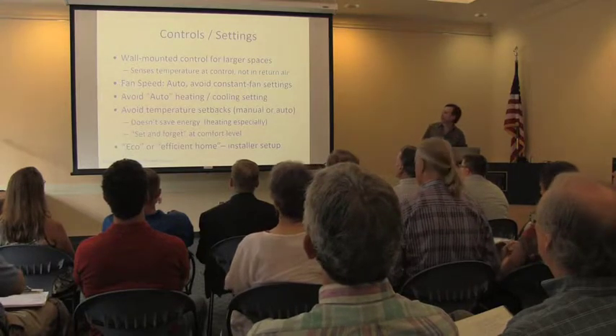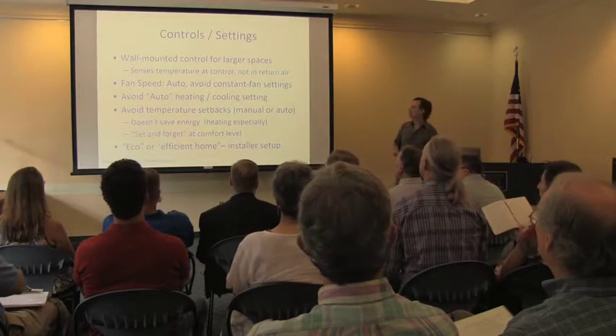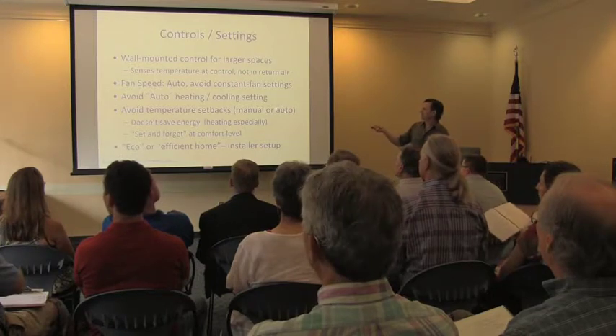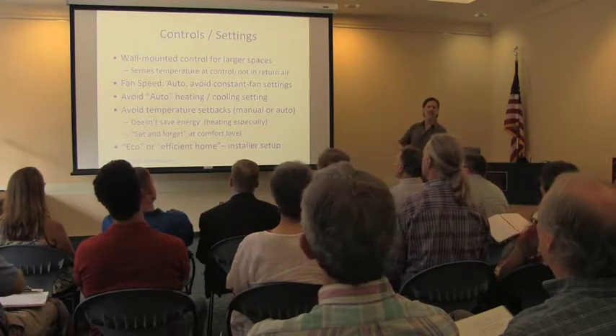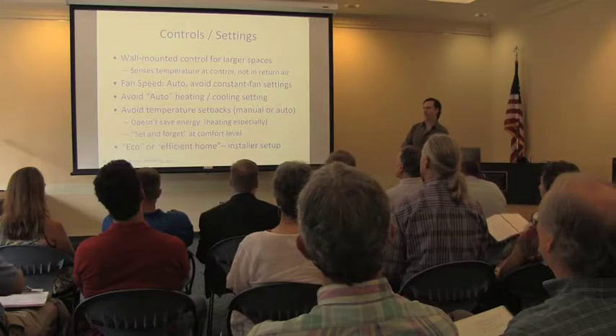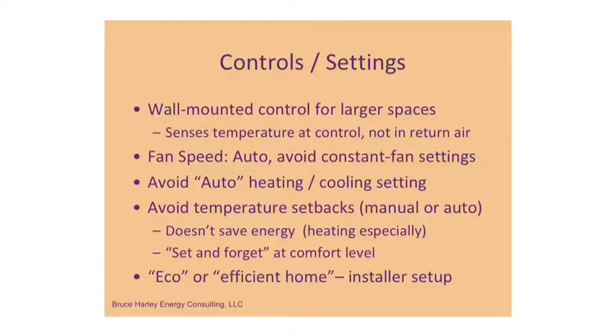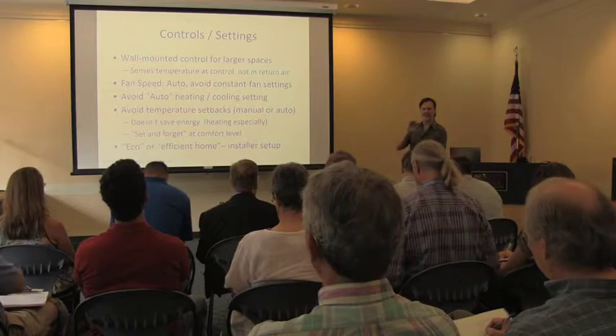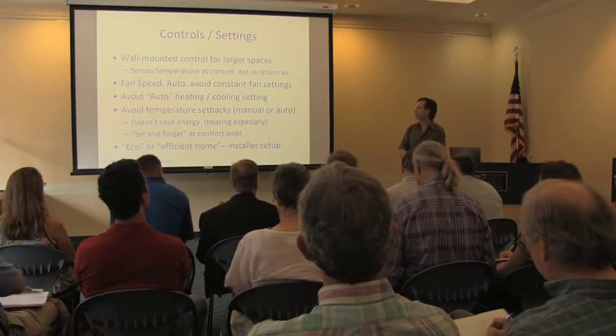There's a few things about controls and settings. Probably the most important of all of these is don't set the temperature back and then up every day. With these variable speed systems, it actually uses more energy, and it's better to set it and forget it, leave it at a comfortable setting, and let it just operate at a slow and steady pace.